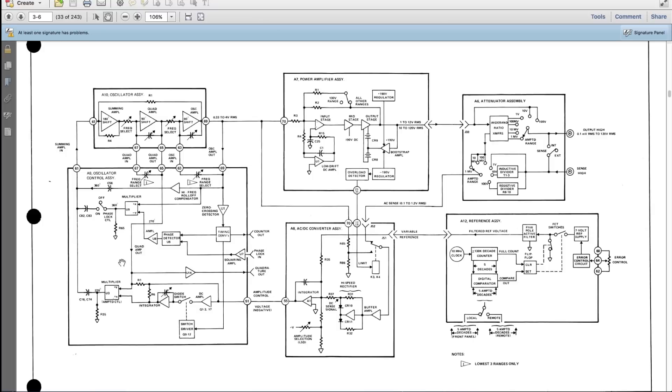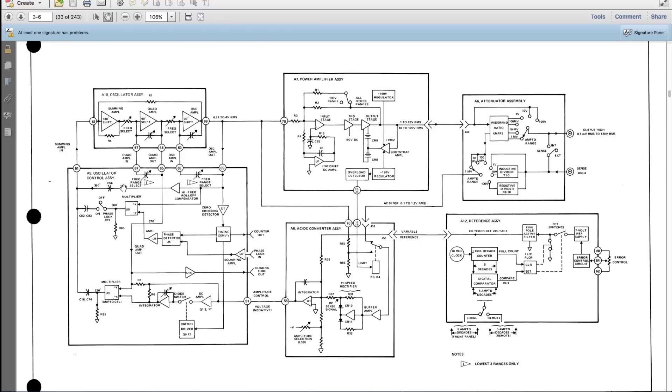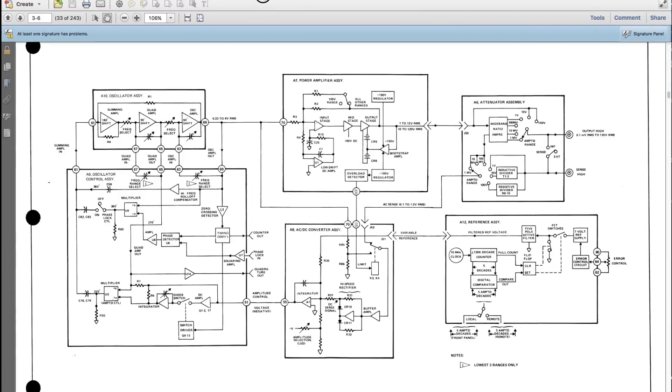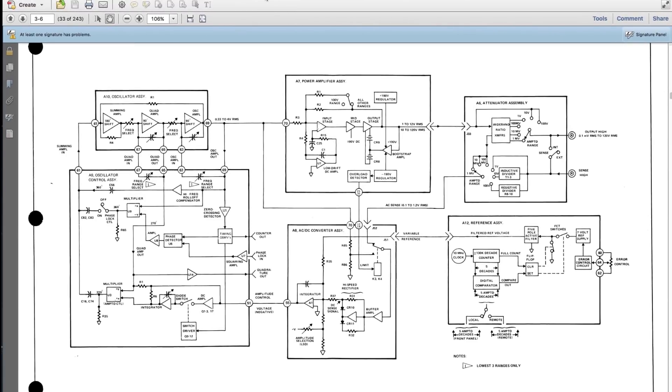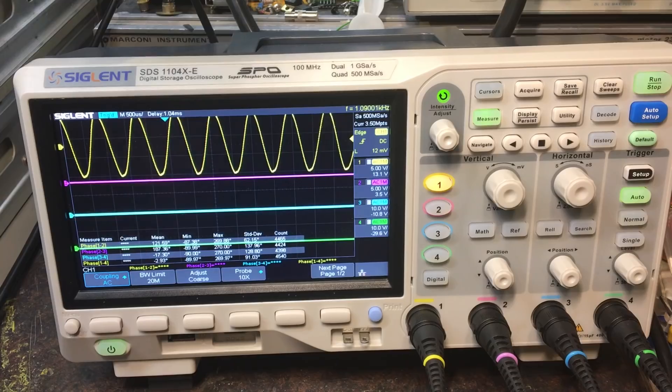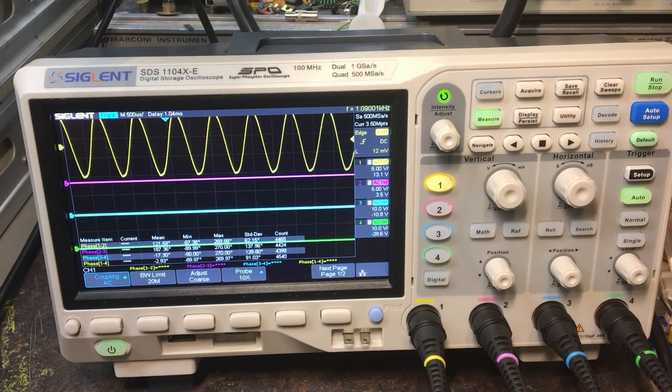I may still go that route yet though. So I actually want to inject a negative voltage here and see if it corrects the frequency here. It probably won't. It's supposed to be for amplitude control, but if this is completely skewed off, it may be trying to do something else. So the phase locked circuit, when it's turned off, it disables. All this isn't used. Any of this isn't used. That doesn't matter. So it eliminates a whole bunch of circuitry. So all it's really doing here is looking at this roll off here and this tuning here. That capacitor there could be bad, C56 for example. The range selections work. Yeah, this unit's been a bit of a pain. It's been a long journey.